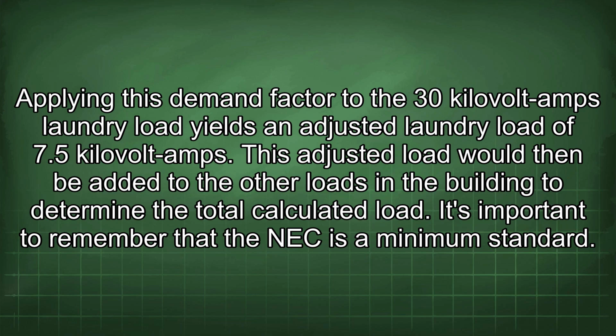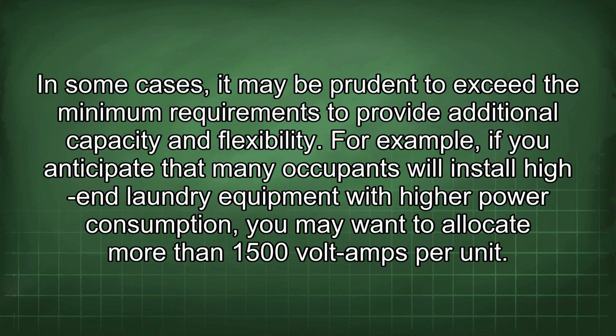It's important to remember that the NEC is a minimum standard. In some cases, it may be prudent to exceed the minimum requirements to provide additional capacity and flexibility. For example, if you anticipate that many occupants will install high-end laundry equipment with high power consumption, you may want to allocate more than 1500 volt amps per unit.